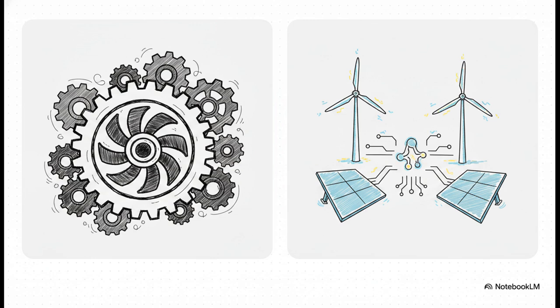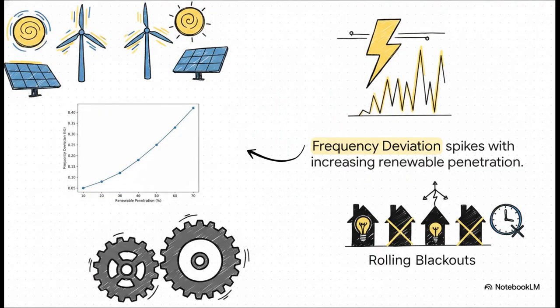But inverter-based resources, things like solar panels and wind turbines, they connect to the grid digitally. They offer almost zero physical momentum, and they provide extremely limited short-circuit fault current. We are essentially trading heavy, mechanical stability for digital efficiency. If you look at this correlation, it is wild. As renewable energy penetration goes up, the overall physical inertia of the power system drops. And when that happens, any little disturbance in the system causes severe spikes in the rate of change of frequency. Without that heavy spinning mass acting as a shock absorber, a simple fault can cause frequency deviations that trigger automated load shedding. In plain English, rolling blackouts, simply because the grid reacted way too fast to a tiny glitch.